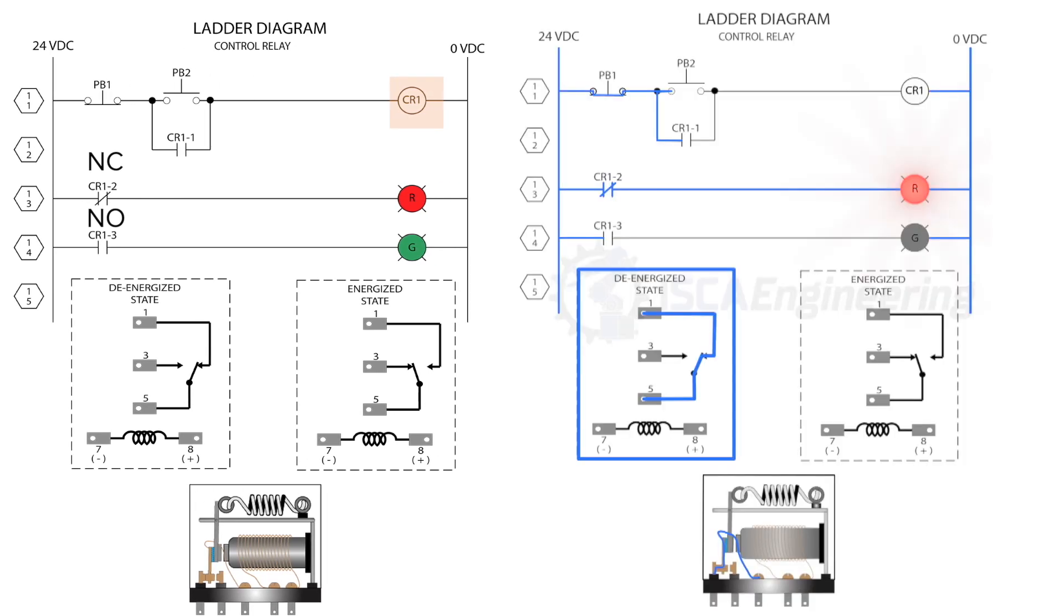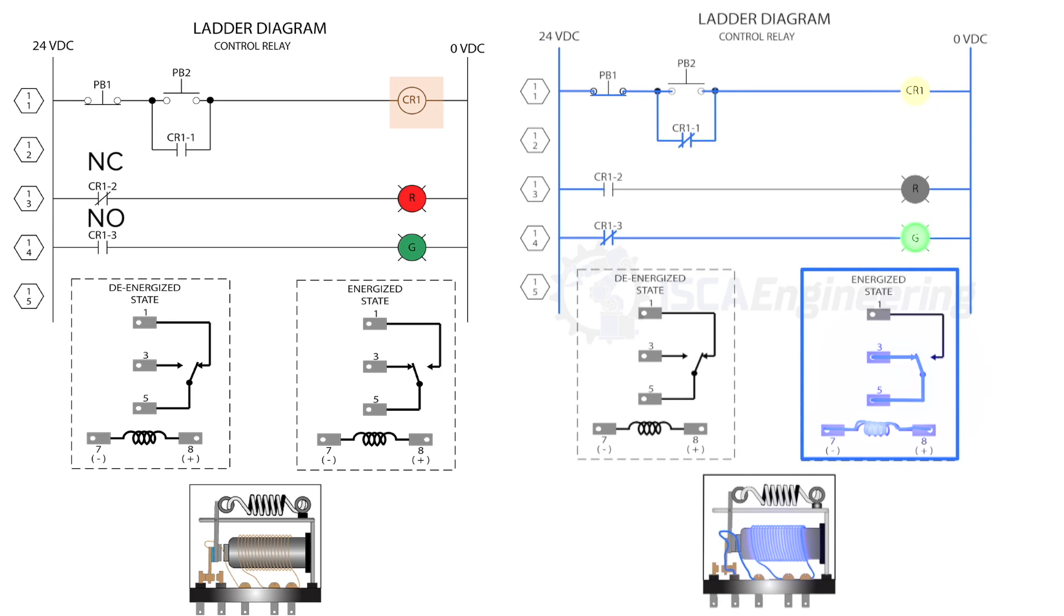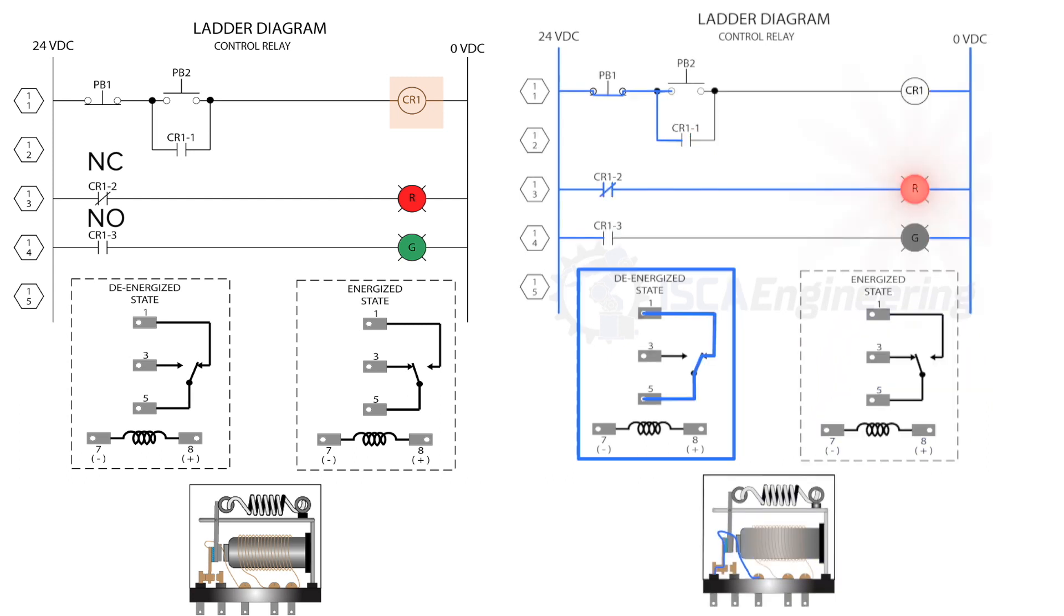In the de-energized state, the normally closed contacts allow current to flow through until the contacts change state. In the energized state, current flows through the normally open contacts until the contact states change. Circuits are shown in their de-energized state. That being said, when the relay coil is not energized, then the red indicating light will come on as soon as power is provided to the circuit.